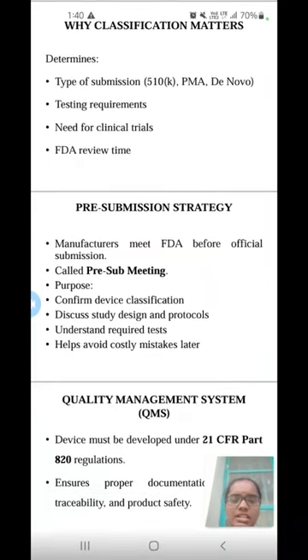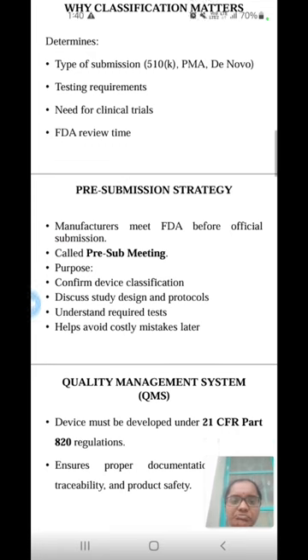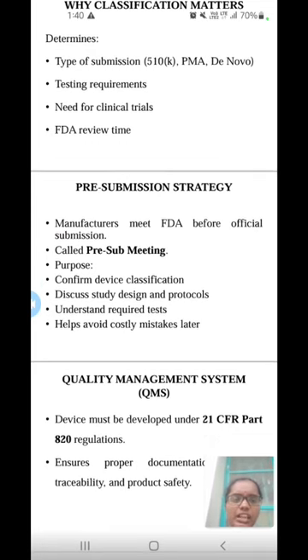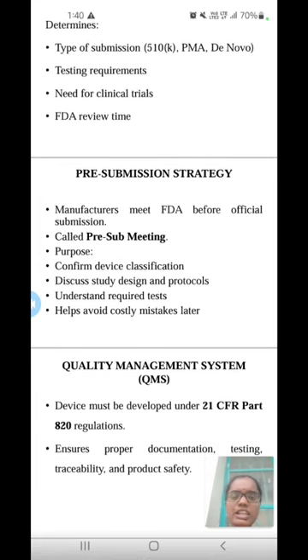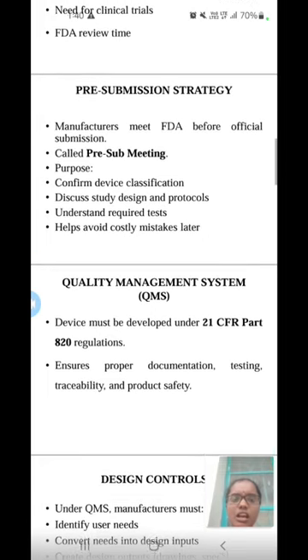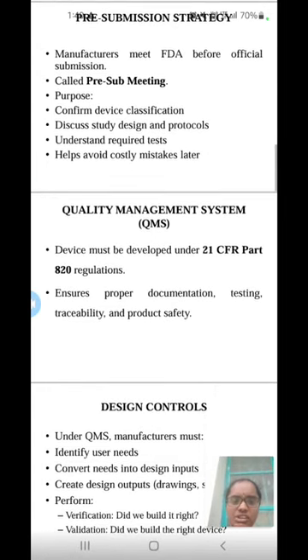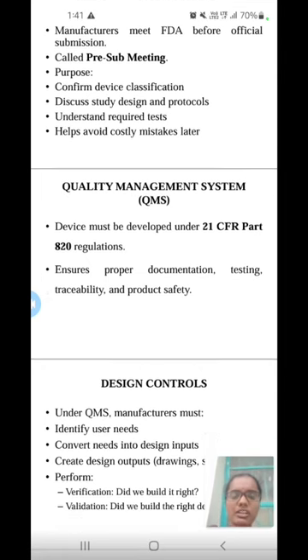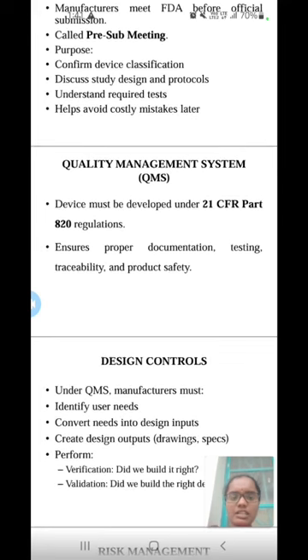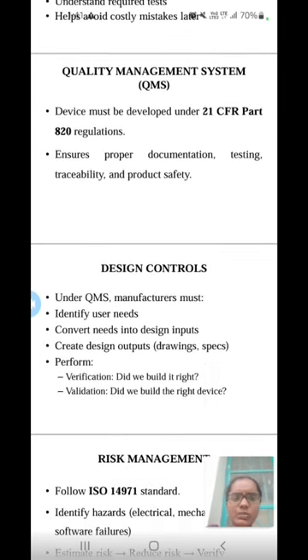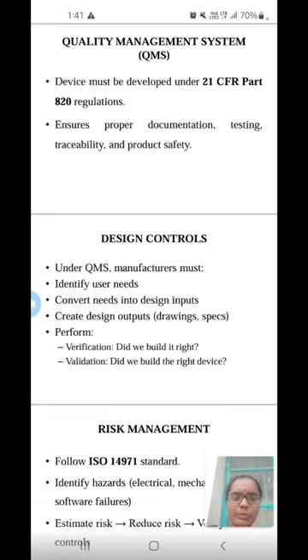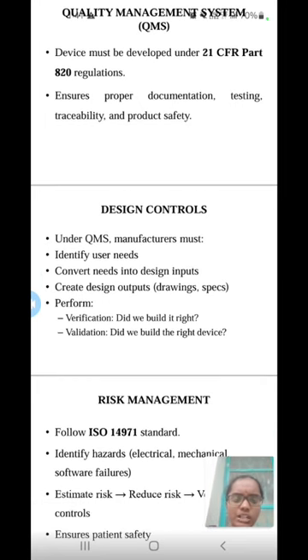Why does classification matter? It determines the type of submission, PMA, 510K, or de novo, the testing requirements, the need for clinical trials, and the FDA review time. Next, pre-submission strategy. Its purpose is to confirm device classification, discuss study design and protocols, and understand required tests, which helps avoid costly mistakes later. In the quality management system, the device must be developed under 21 CFR Part 820 regulation, ensuring proper documentation, testing, traceability and product safety.